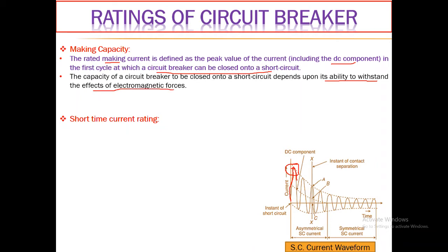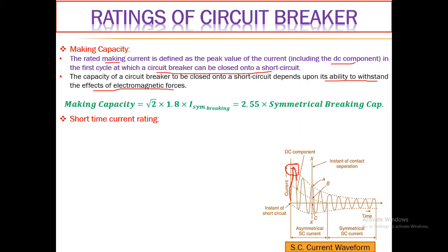The capacity of the circuit breaker to close onto a short circuit depends upon its ability to withstand the large electromagnetic forces. When short circuit current is 8 to 10 times the normal rated value, large electromagnetic forces develop causing vibrations that may seriously damage the contacts. Making capacity is calculated as: Making Capacity = √2 × 1.8 × Symmetrical Breaking Capacity = 2.55 × Symmetrical Breaking Capacity, where 1.8 represents the DC component and √2 converts RMS to peak magnitude.